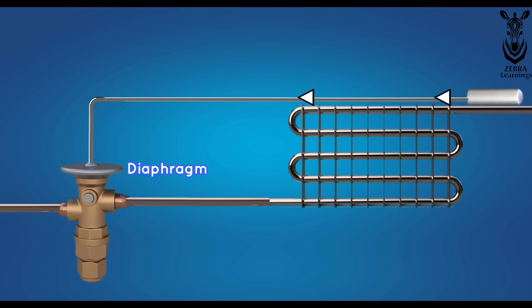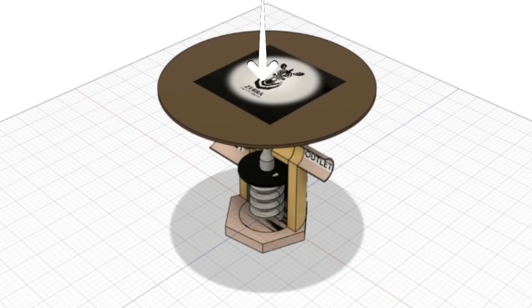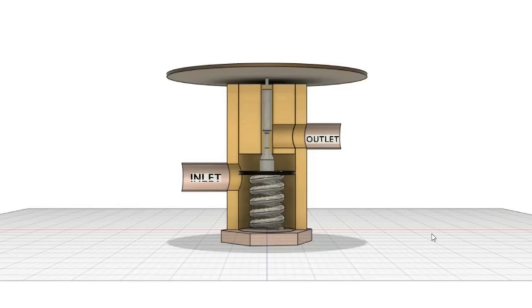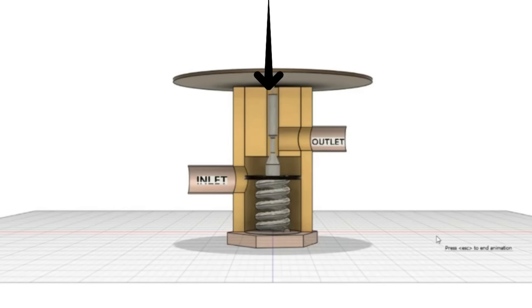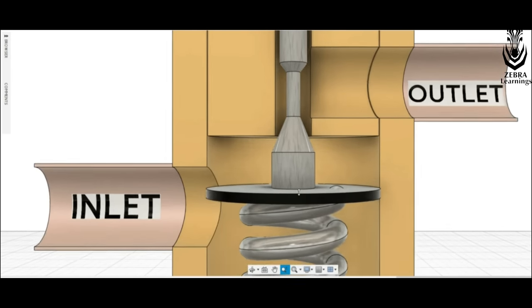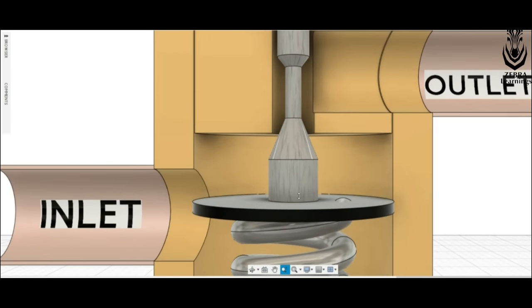All this vapor comes through this small tube to the diaphragm in the expansion valve and pushes the diaphragm down under high pressure. This diaphragm is connected to a spring inside the expansion valve. When the diaphragm is pressed down, this spring is also compressed. Now, the refrigerant path increases, and more refrigerant goes to the evaporator.